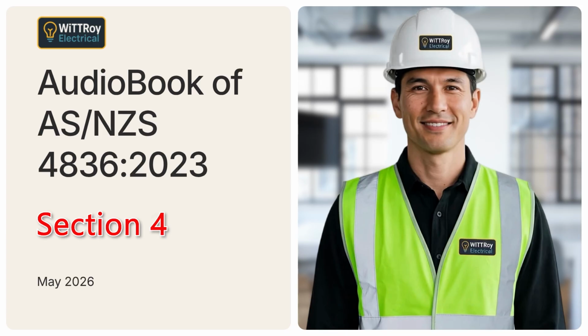Clause 4.3.1. Work on or near exposed energized conductors and live conductive parts. Clause 4.3.1 explains work on or near exposed energized conductors and live conductive parts. The first safety message is very clear. Working on energized circuits and equipment is not as safe as working de-energized. So work on or near exposed energized parts should only be carried out in limited situations. It may only proceed where it is necessary in the interests of safety, or where de-energizing the equipment would create greater risk, and where the required risk controls have been carried out. The worker must be competent. In some workplaces, the relevant authority, employer, or organization may also require specific training and authorization before the work can proceed.